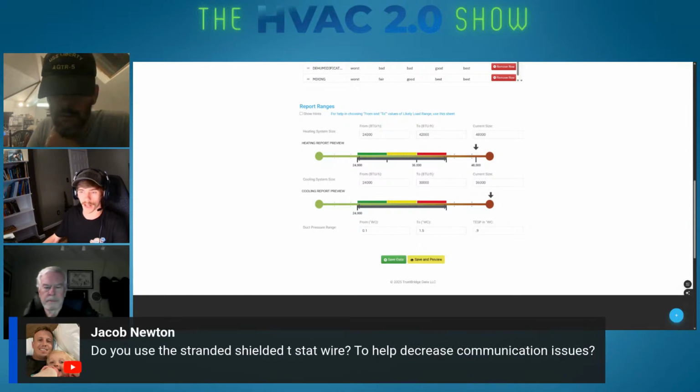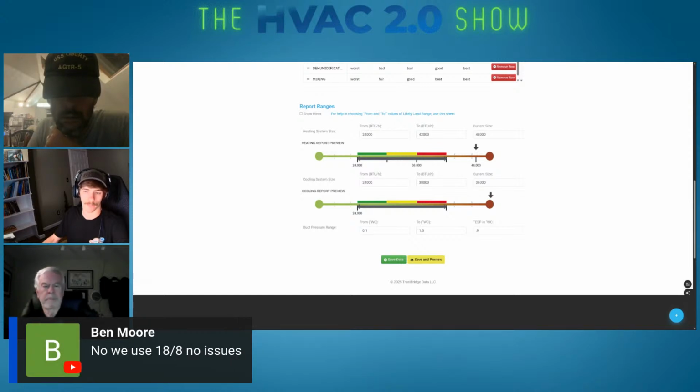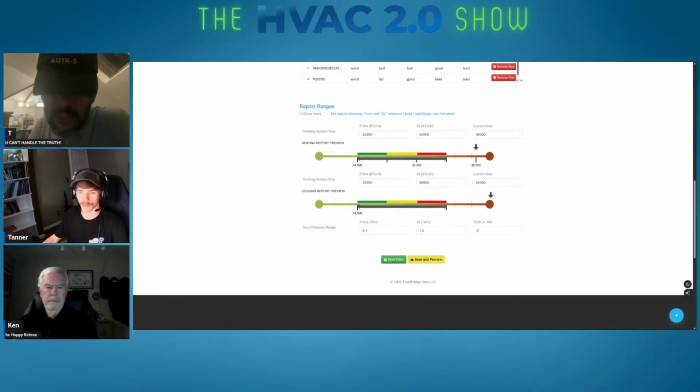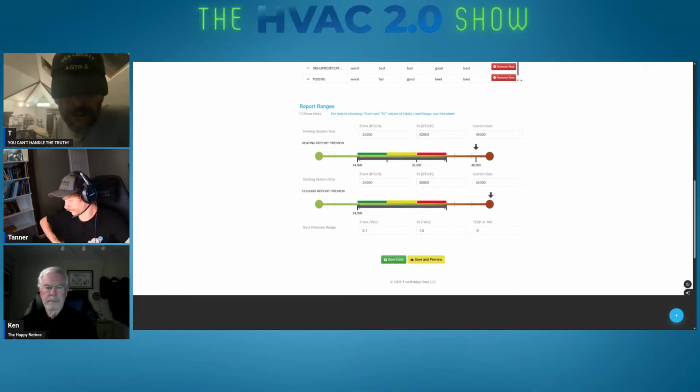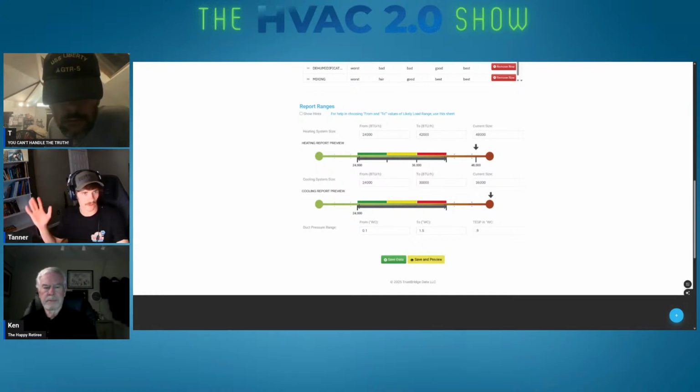And just to highlight the discussion here, for pretty much any residential communicating systems, it's just thermostat wire. The additional cost is well worth the safety factor. It's not until you get into commercial, if you're talking Fujitsu VRF with their pink stranded wire, that only that particular wire works. That's really only much of a problem in commercial settings, just because you've got a lot more going on. Then it's a lot more expensive.